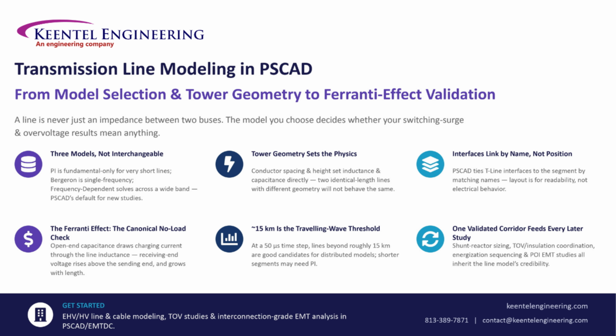Once built, the classic validation is the Ferranti effect. With the receiving end open, the line's capacitance draws charging current through its inductance, and the receiving end voltage rises above the sending end. That single check drives real decisions, from shunt reactor sizing to insulation coordination.